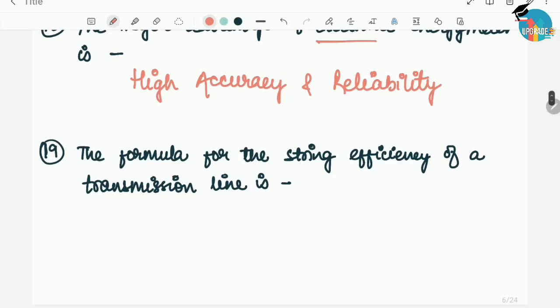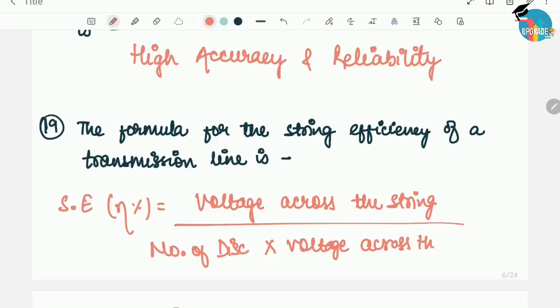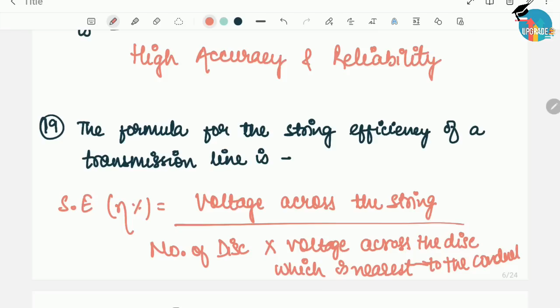Next question is, the formula for string efficiency of a transmission line is given as the voltage across the string divided by the number of disc insulators, multiplied by the voltage across the disc which is nearest to the conductor. By this formula, string efficiency can be calculated. A simple formula question was asked about string efficiency.